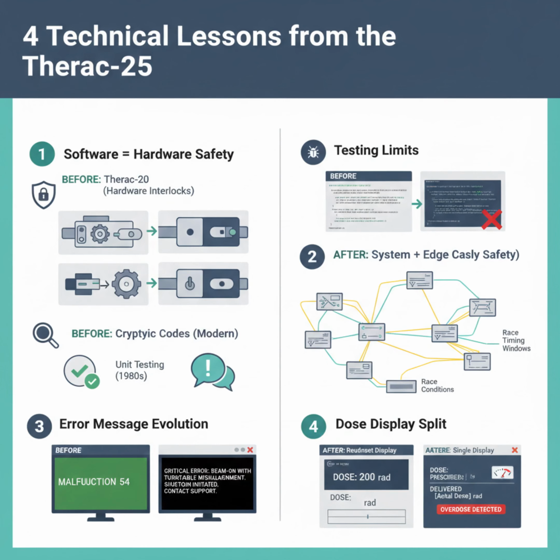The malfunction 54 error operators saw was a cryptic message triggered by an unrelated safety check, an overflow in a dose monitoring counter. But the error message gave no indication of what had actually gone wrong. The manual described it as a routine fault that should be cleared and ignored. Worse, the dose display showed the prescribed dose, not the delivered dose. Even after a massive overdose, the screen told the operator that everything was fine.